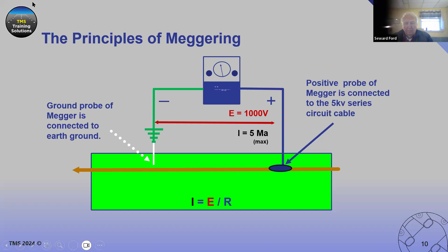Now, our goal in our measuring here, what is our goal? Our goal is to measure the change in resistance between the conductor and path to the megger. In order to observe this change and develop an accurate history, we must be consistent. That's the key. There are variables when we do megger testing. The ground may have a different resistance one day than it does at another because of moisture content.